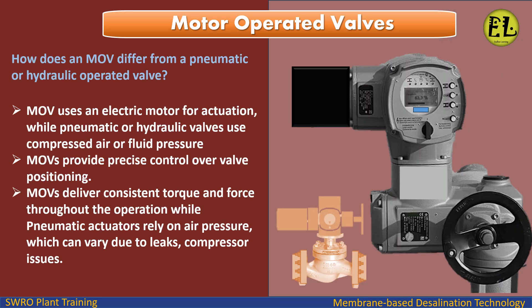How does an MOV differ from a pneumatic or hydraulic operated valve? An MOV uses an electric motor for actuation, while pneumatic or hydraulic valves use compressed air or fluid pressure. MOVs provide precise control over valve positioning and deliver consistent torque and force throughout the operation, whereas pneumatic actuators rely on air pressure which can vary due to leaks or compressor issues.